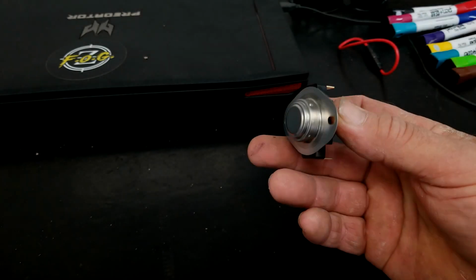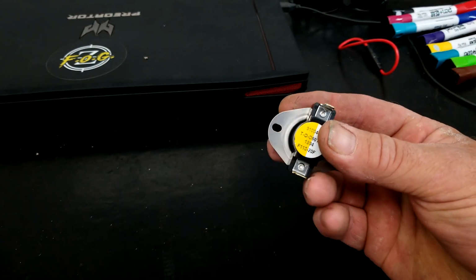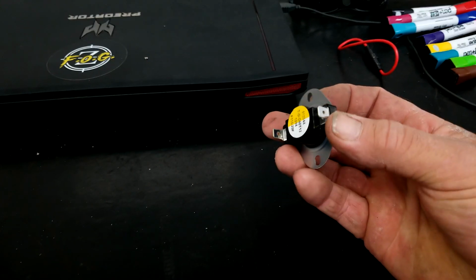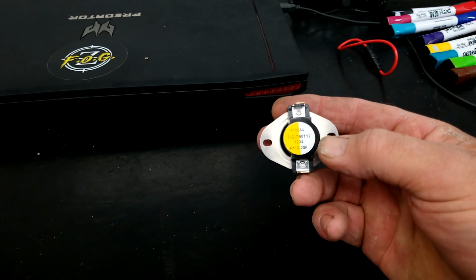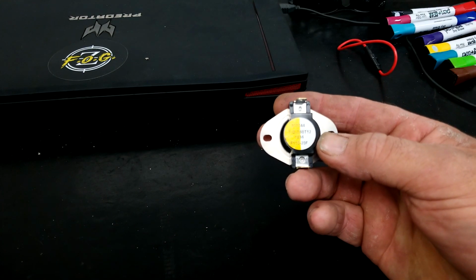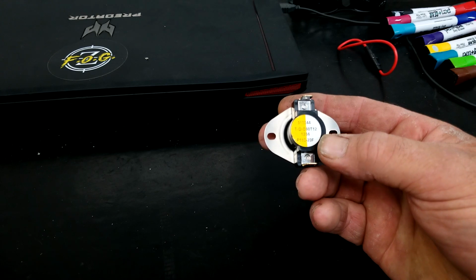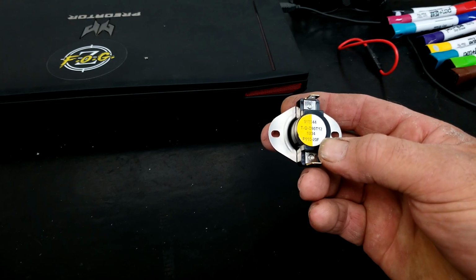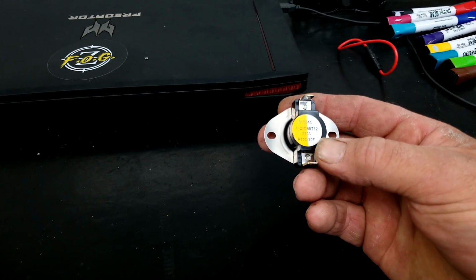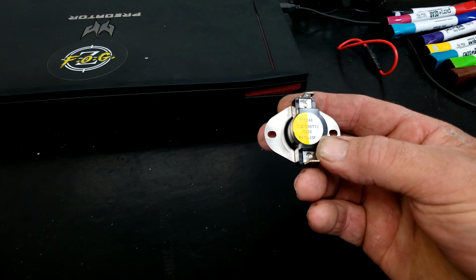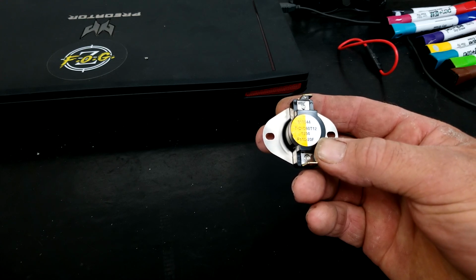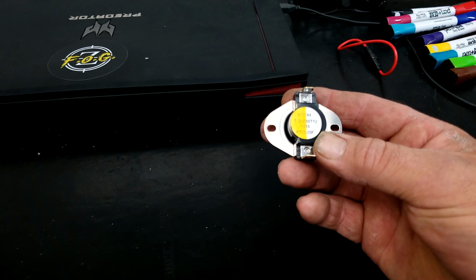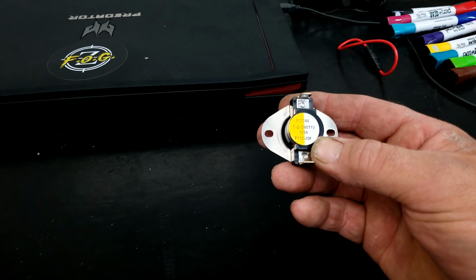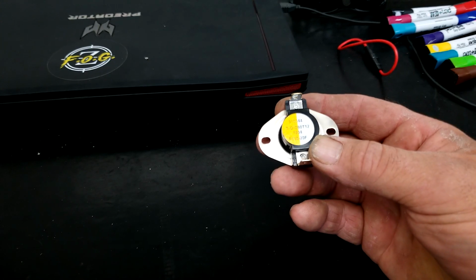Next up is a small thermal switch. All this does is control the fan. There's 2 different types available. This is a fixed value. This one will kick on at 110 degrees, so it closes on rise. That's important. The switch closes on rise and opens when the temperature drops. This has got a 20-degree deadband, but it actuates at 110 degrees.